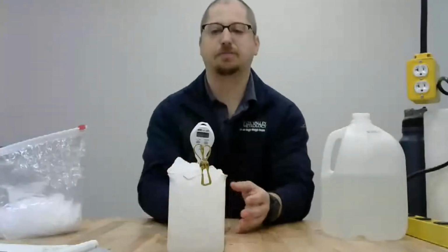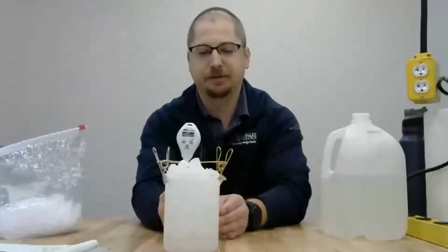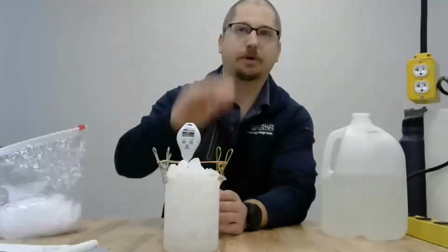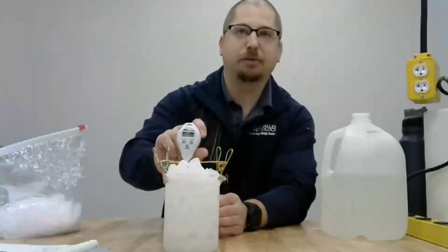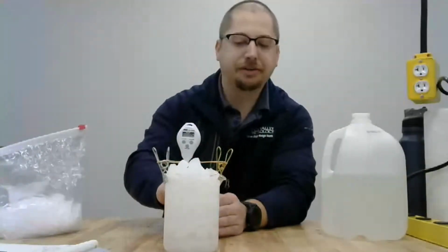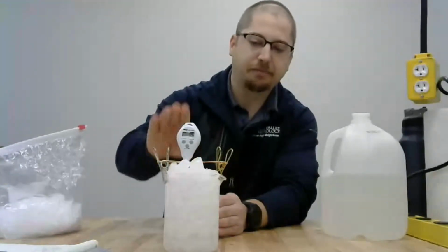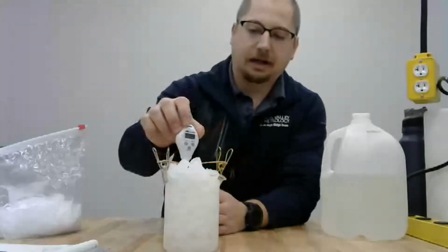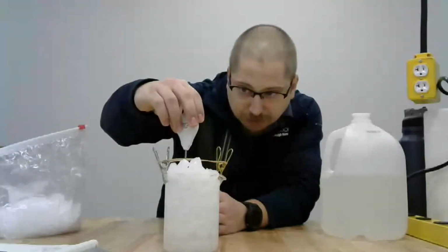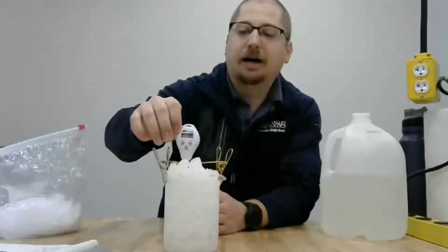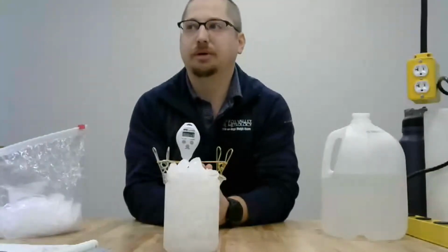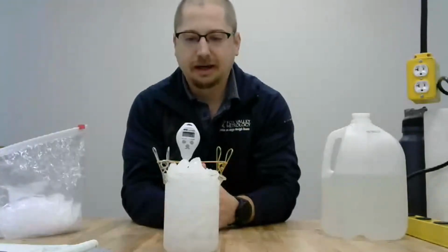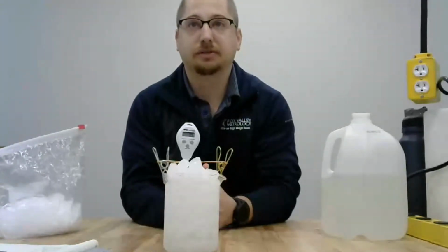If you want to keep that ice point for that longer period as well, all you have to do is, as the ice begins to melt, drain off a little bit of that water and repack the top of it so that there's that buffer back on the top. As long as it's not melting continuously and you have a lot of water on the bottom, this is a sound ice bath or ice point reference. You can see here that our thermometer is still slowly going down. If I had a recording, then I would skip this step and show you the end result of when the temperature is actually settled. But that will take several minutes.